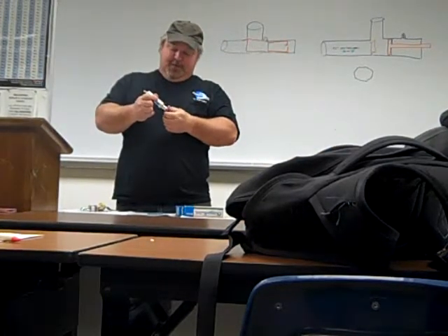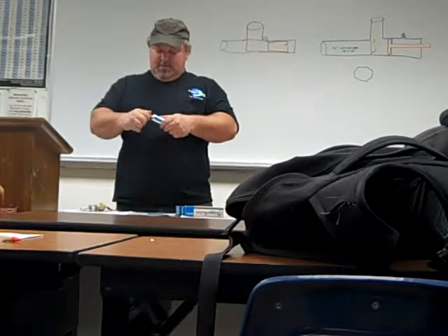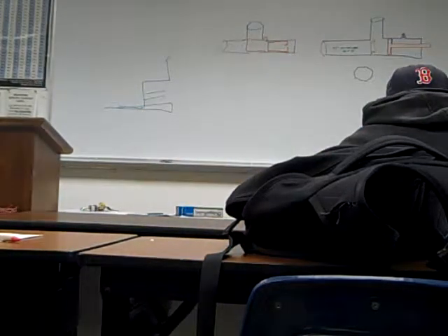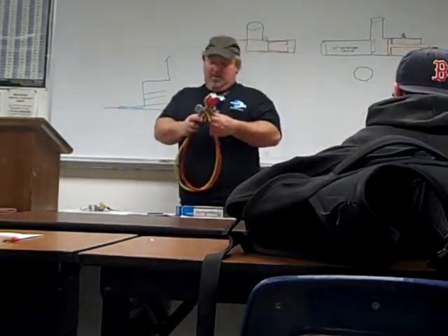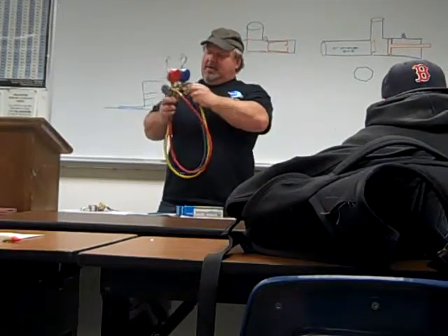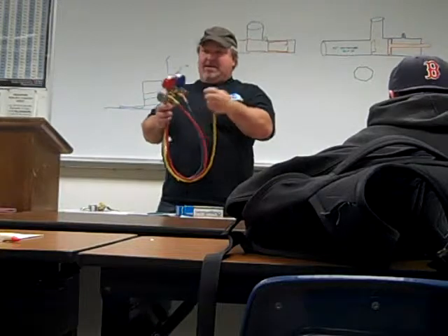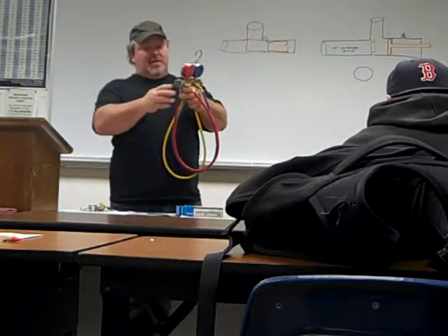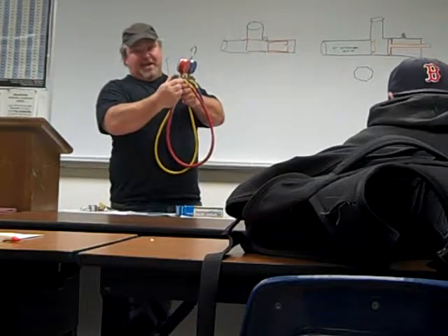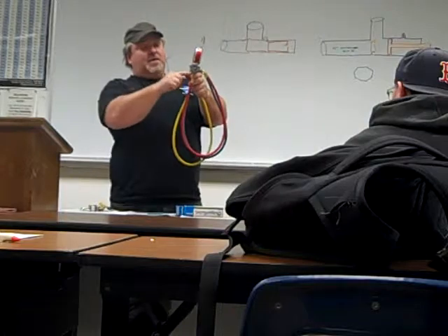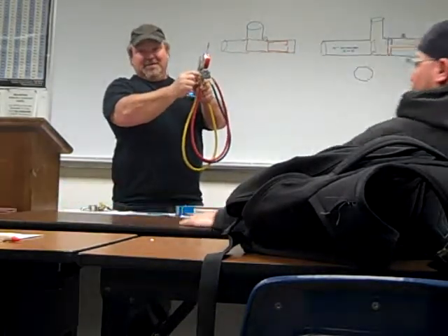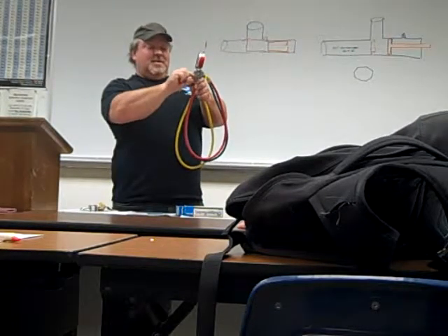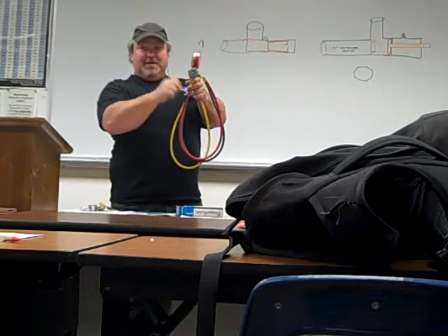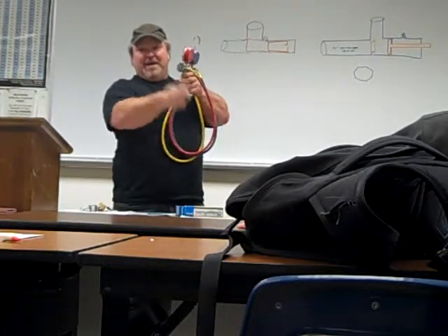I'll pass this around. But I always tell my guys, if you don't have something like this, you can take a regular hose set and you hook the yellow line up to your tank, and hook the blue line up to your low side and the red up to your high side. Whenever you're charging it as a liquid, you just take this and you barely crack this thing open. And you're letting liquid come up into here, but you're using this point in here as a metering device. So it flashes off. It's all liquid right there, but it's being metered here. It's coming from a higher pressure to a lower pressure. So it's turned into a vapor. And it's all vapor then when it comes out here and goes into your system.